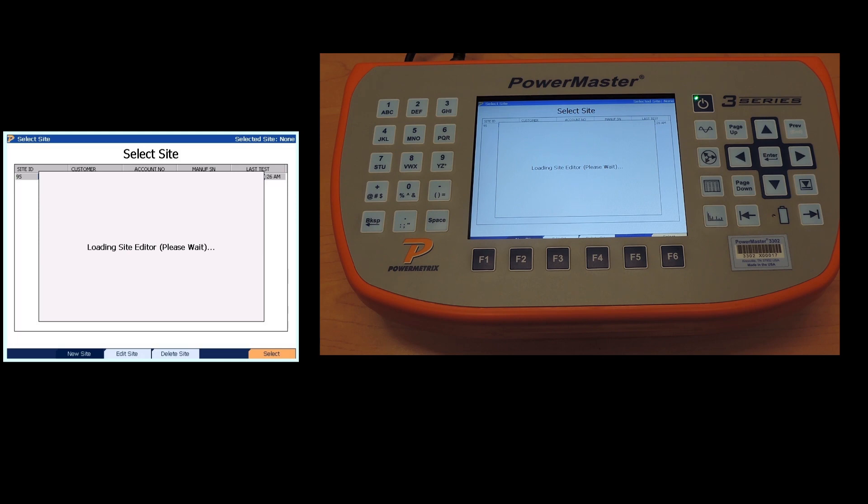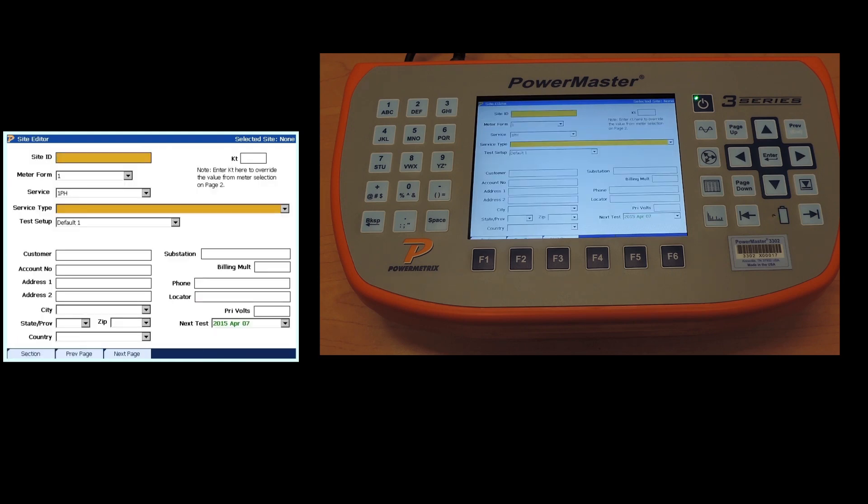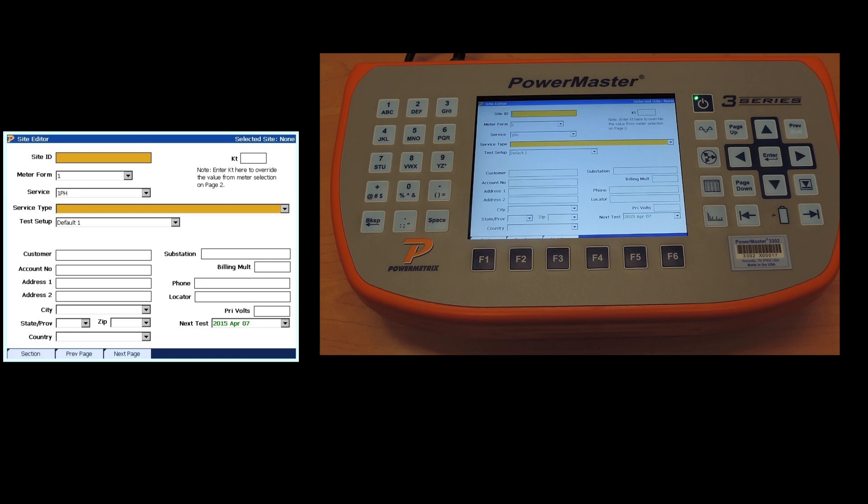When you're selecting your site ID, it needs to be something specific and unique to that area. A site is the meter plus all the instrumentation transformers that are fed into that particular meter. If you're in a facility that has multiple meters, you have multiple sites. You don't want to use anything like the meter ID or the meter number because meters can be changed. A good thing is location ID, transformer number, something that's not going to change.